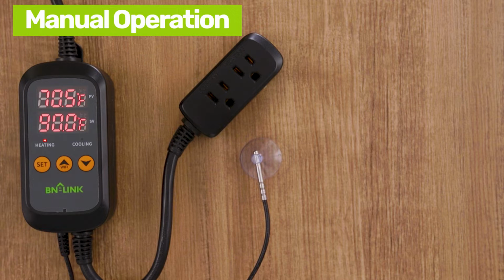First, let's find the middle temperature between our highest temperature and lowest temperature. For example, if we want to have the cooling start at 90 degrees and our heating to start at 70 degrees, our middle temperature will be set at 80 degrees. Since 80 degrees is the middle of our two temperatures, it is best as the set temperature.